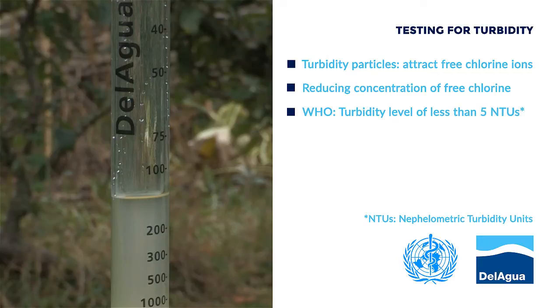The World Health Organisation suggests a turbidity level of less than 5 NTUs for drinking water safety when used in conjunction with a free chlorine reading of 0.2 mg per litre.